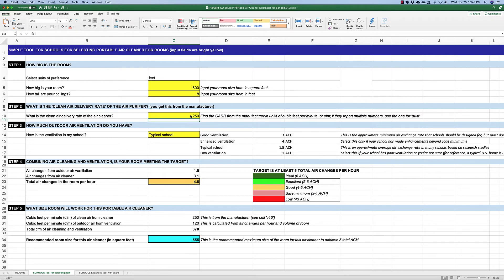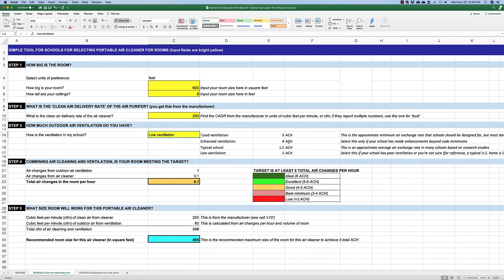For a typical school, you would decide on the ventilation rate by clicking here and selecting low ventilation, typical school ventilation, enhanced ventilation, or good ventilation. With low ventilation — less than or equal to one air change per hour — adding the one air change from outdoor air and 3.1 air changes from the air cleaner gives a total of about four air changes per hour. You can also determine that a 250 CADR air cleaner should really only be used in a room about 500 square feet.